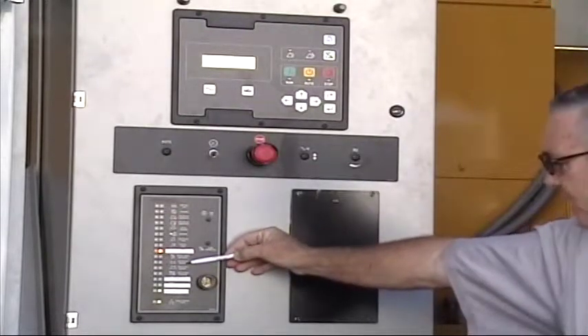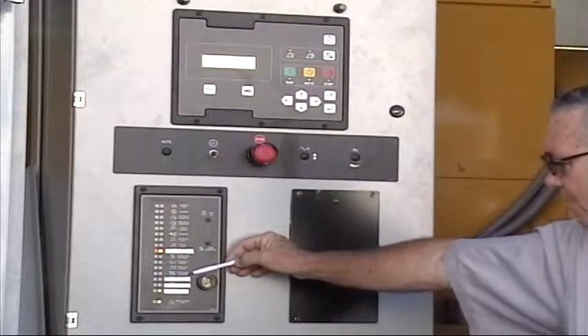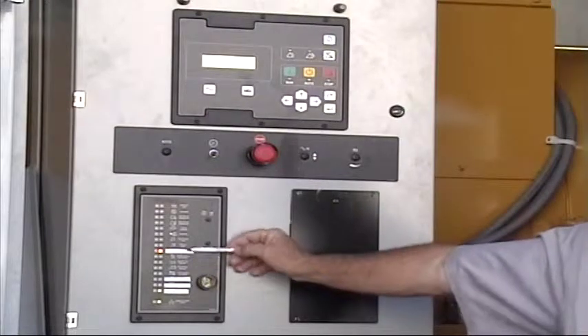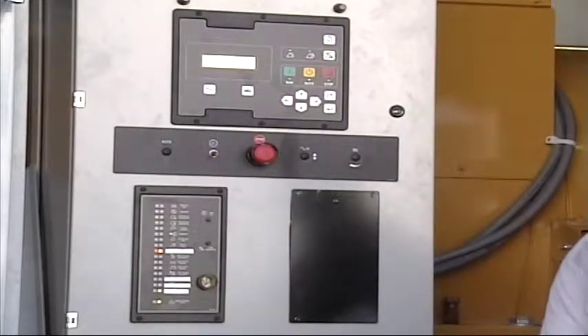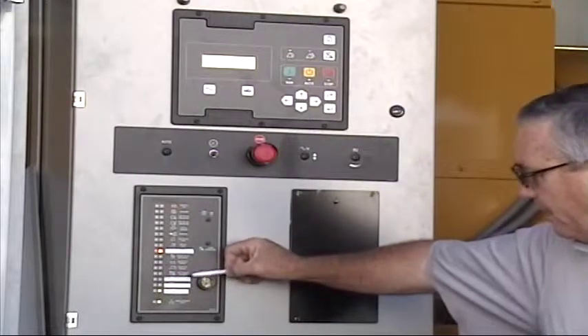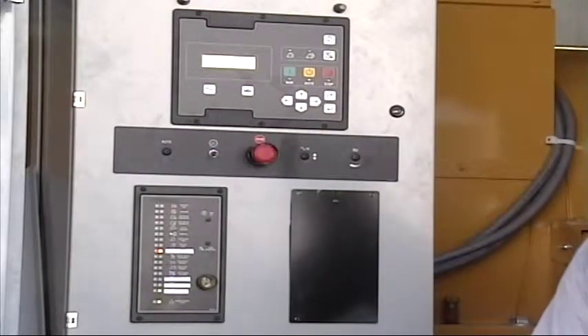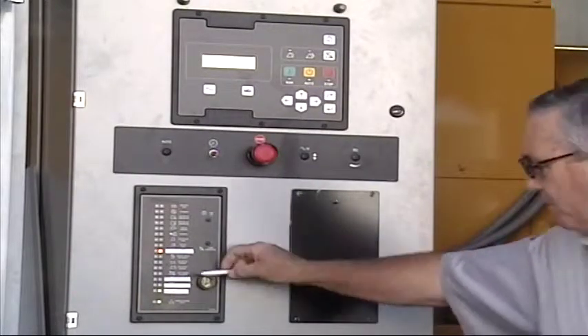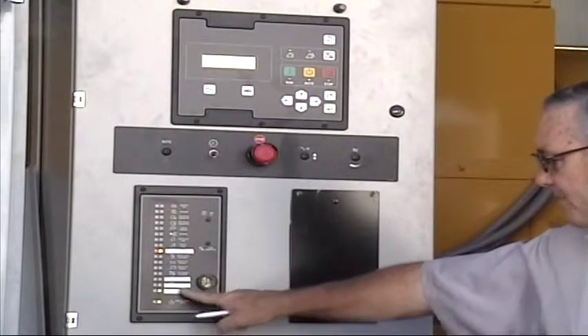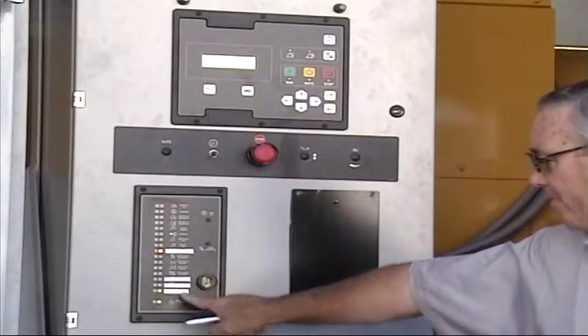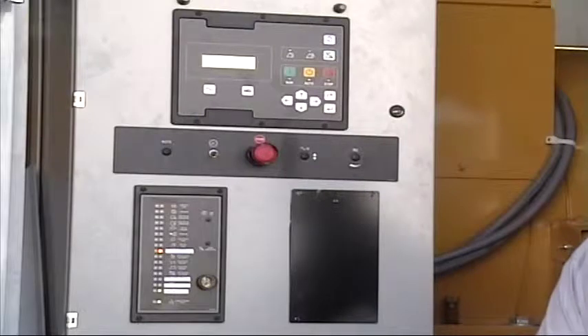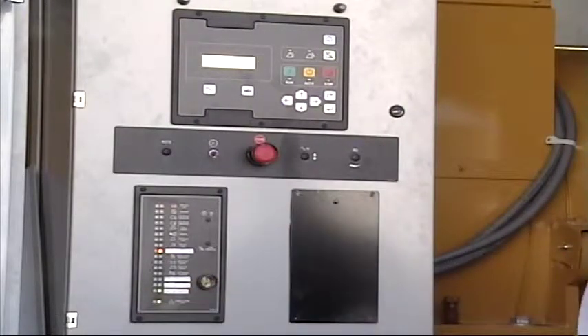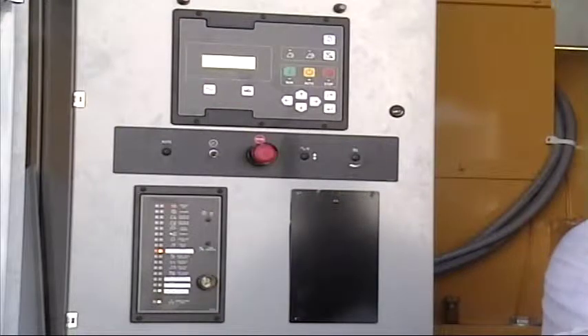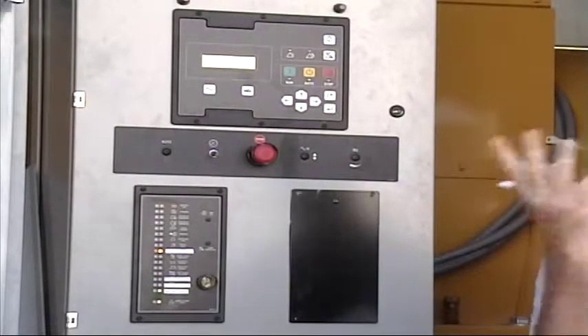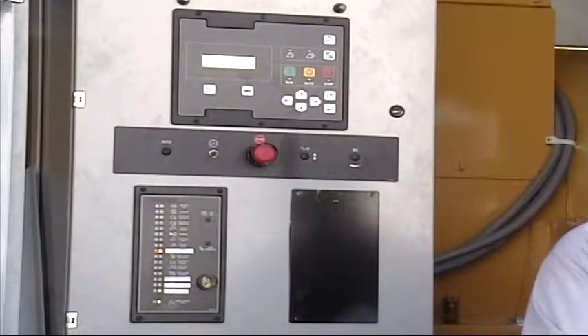High battery voltage, low battery voltage, battery charger, AC failure — obviously those are all connected to batteries. They're going to be alarms that you'll get. Fuel tank leak, that's what I asked Nathan about, rupture basin we call it, there's outside, E-stop, and generator circuit breaker status. And does that go red? Yes, that'll go red when the generator breaker is closed. So right now, the position we're in, generator breaker's open, okay?